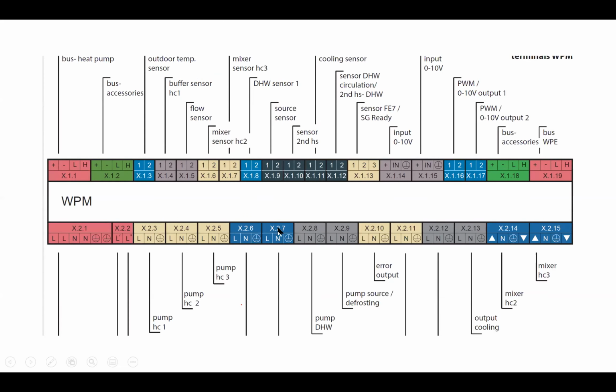What you will note then, if I go back to the WPM wiring, the X113 gave us mode changing from the actuator manifold module. There aren't any extra terminals just to put extra thermostats in. You can't go and buy 3 Siemens thermostats and wire them into our WPM to bring on the heating circuit pumps. It doesn't exist.